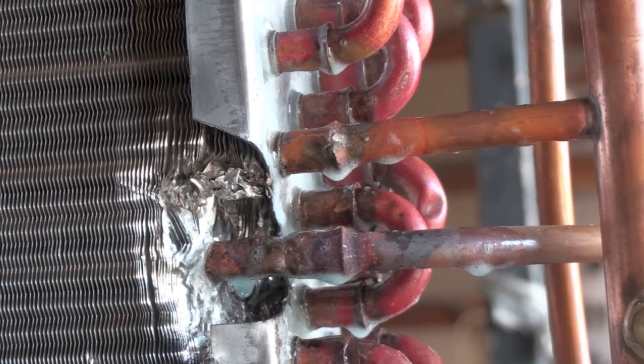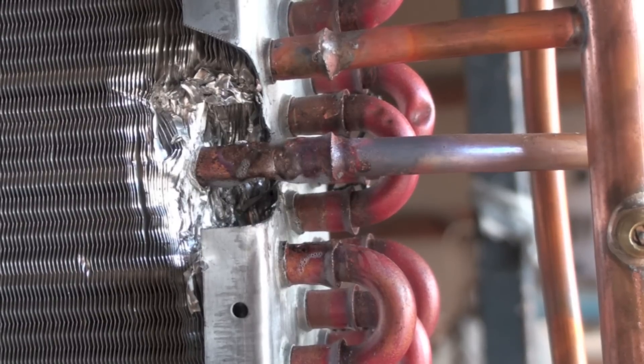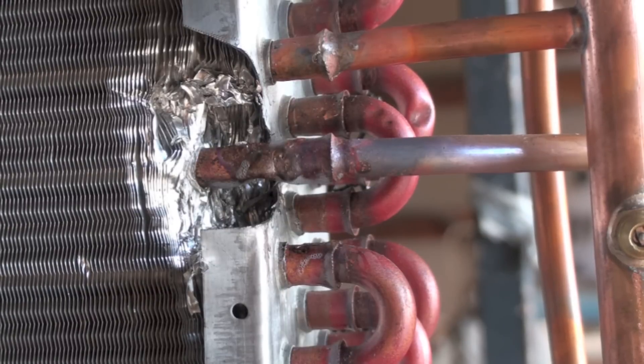In summary, this is a viable repair. It was not done on this piece of equipment — the entire unit was replaced. But I would think probably an hour spent cleaning this up and soldering that pipe would put you back in business. So I think this is a viable repair.